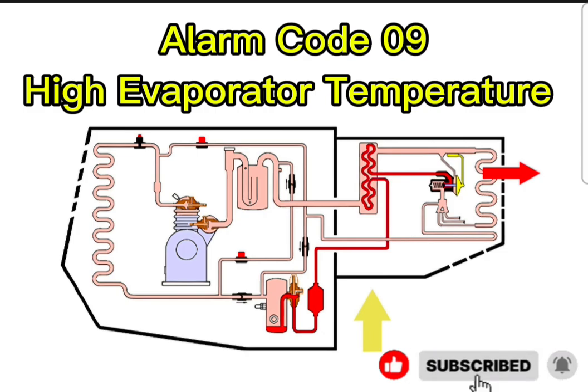Think of a damper as a large physical door or a louvered vent within the ductwork. Okay. When the hot gas solenoid opens to melt the ice, you don't want all that localized heat blowing out into the main trailer where the frozen food is stored. Right, you'd ruin the cargo. So the system actuates the defrost damper, physically closing a door over the coils. It traps the heat in a tiny, confined space right around the frozen metal, maximizing the melting efficiency and protecting the cargo. Okay, I see the trap.